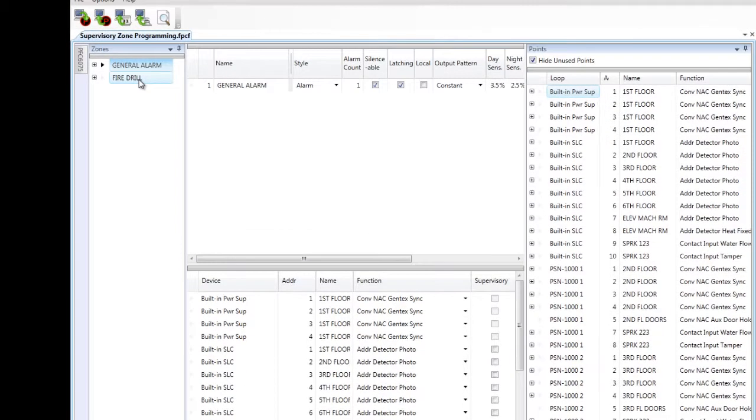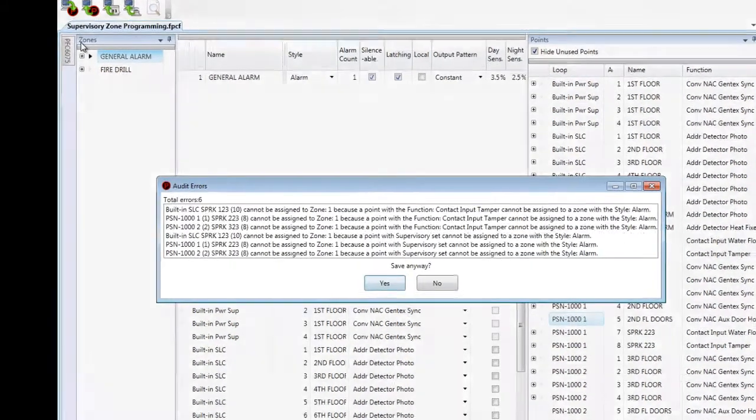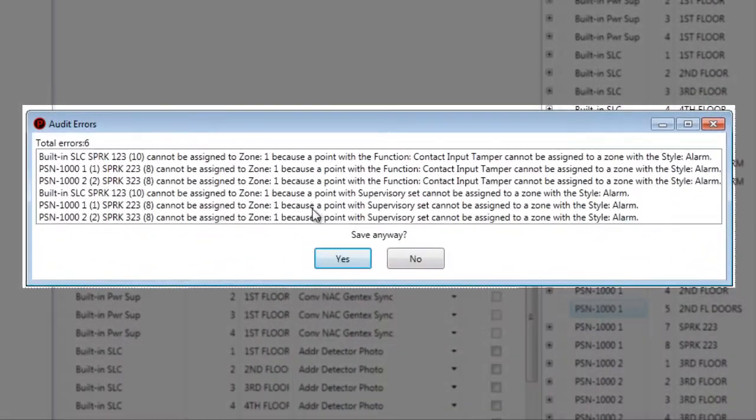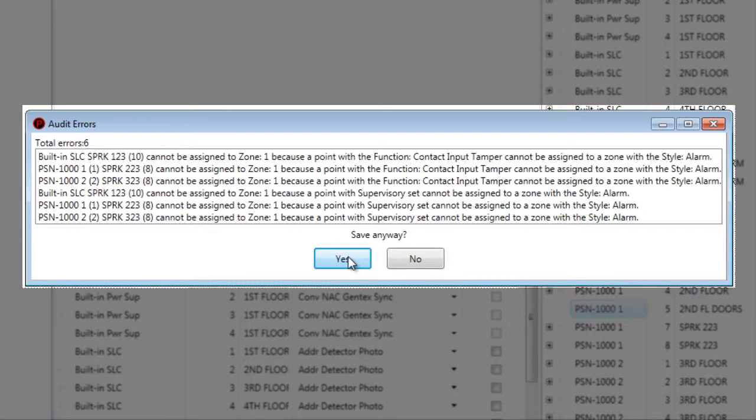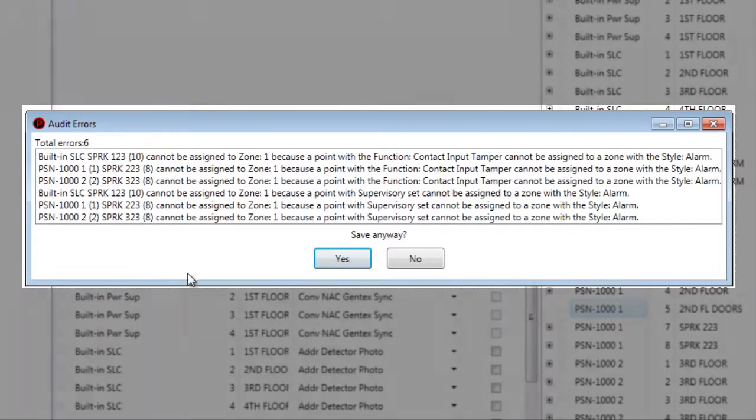If I try and download this into my fire alarm control panel at this point, it will not let me do so because there are audit errors. As you can see here, there are several points that are actually a supervisory point assigned to the alarm zone, and that will not work.